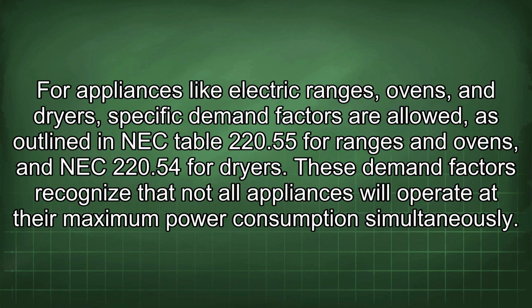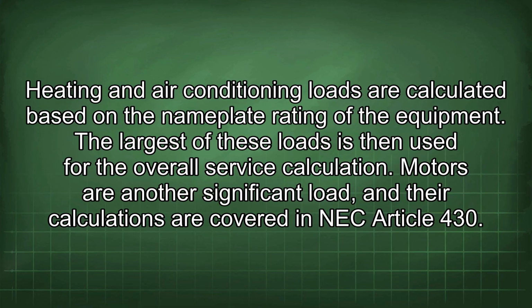For appliances like electric ranges, ovens, and dryers, specific demand factors are allowed, as outlined in NEC Table 220.55 for ranges and ovens, and NEC 220.54 for dryers. These demand factors recognize that not all appliances will operate at their maximum power consumption simultaneously. Heating and air conditioning loads are calculated based on the nameplate rating of the equipment. The largest of these loads is then used for the overall service calculation.